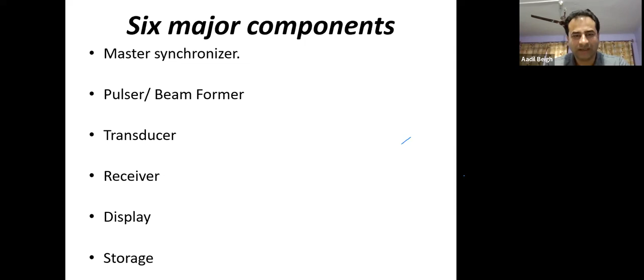So the master synchronizer is the brain of the ultrasound machine. It organizes the timing and function of the individual components in order to operate as a single integral system. The pulser creates electric signals to stimulate the piezoelectric material. It's determined by the pulse repetition period, that is the time between the two pulses generated.